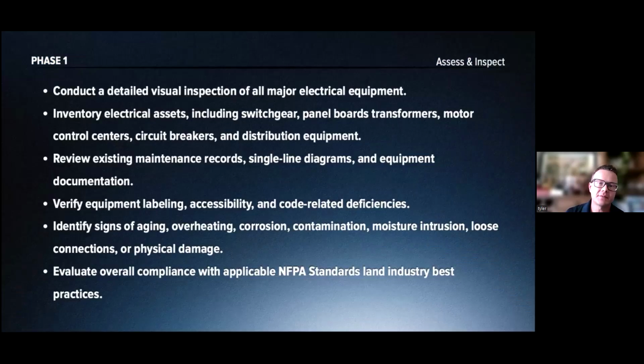So conducting a detailed visual inspection of all major equipment, going into your main electrical room, checking to see if the covers are good, if they're sealed correctly, if there's water in there, condensation potentially in the room, if it's overheating. Also checking for a potential arc flash, any black smoke coming out of the gear - that could be concerning, signaling some underlying issue underneath that cover.